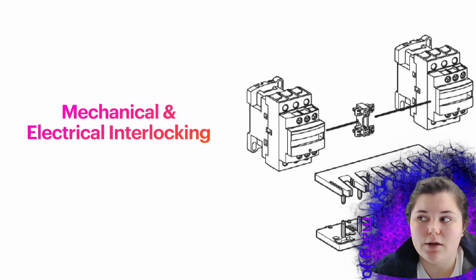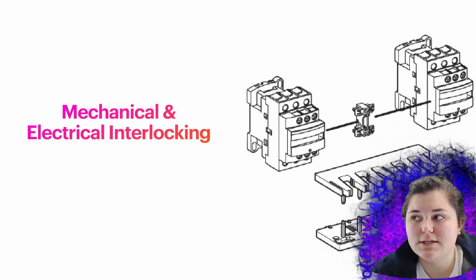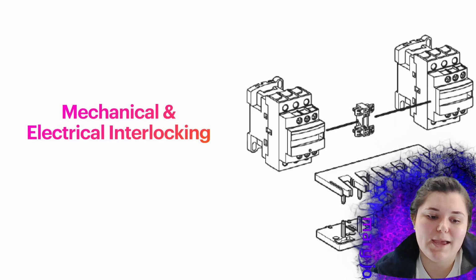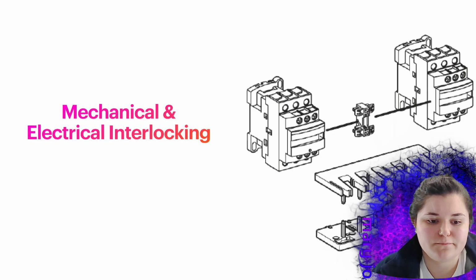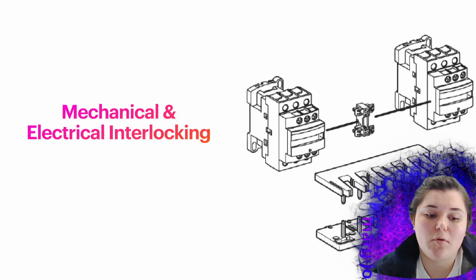Mechanical and electrical interlocking. So this is what it would look like if you put two contactors together to form a mechanical and electrical interlock. And we're going to do that in the lab for one of our labs in the future. So what is a mechanical interlock used for? It's used to physically prevent both contactor armatures from being closed in at the same time. It disables one contactor. So mechanical interlock is used as a last resort. Electrical interlocking is what you should rely on.